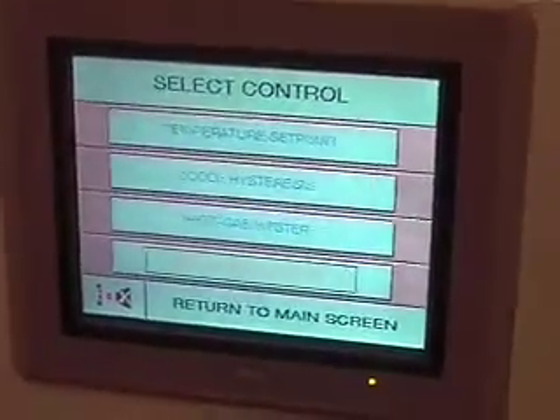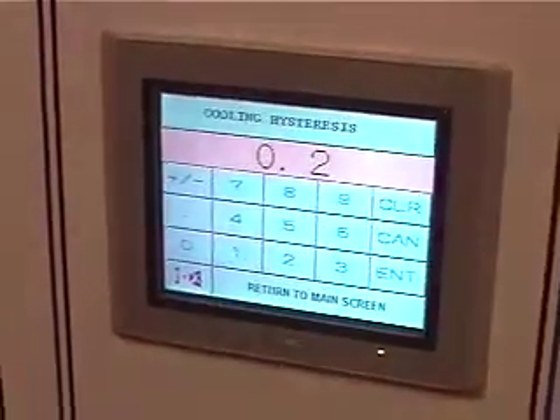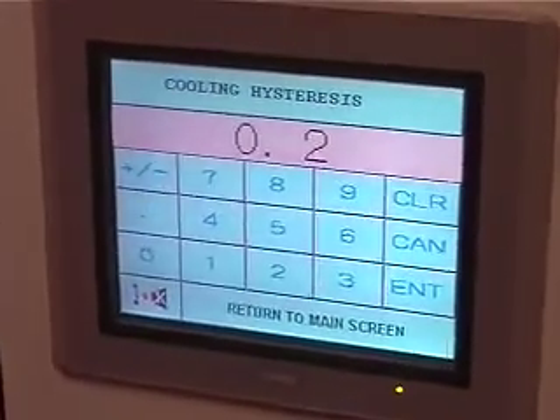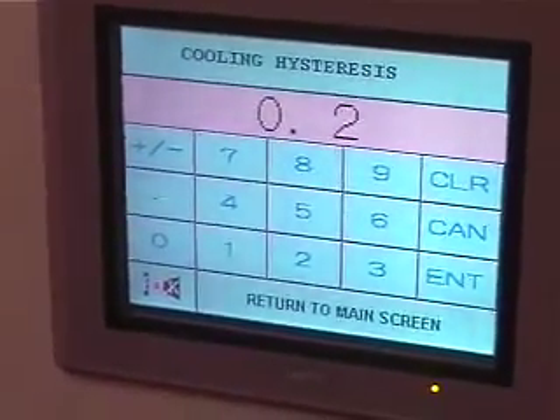Now, on any screen setup, there's 1 or 2 exceptions. We'll cross those in a second. Cooling hysteresis and hot gas hysteresis, that's how we control the solenoid valves. Cooling obviously is for liquid, and hot gas is the hot gas valve. They may operate a little differently than what you might think. At set point, we consider that good. So we don't stop things at set point like we would a regular refrigerator.